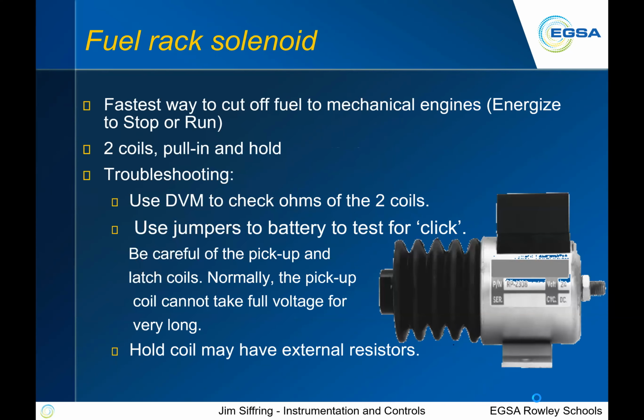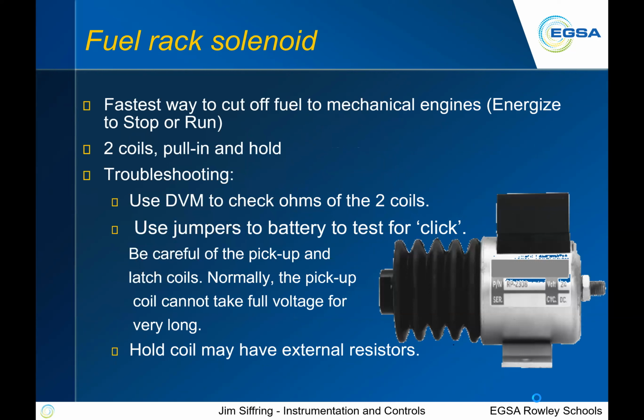Fuel rack solenoids. So, a mechanically injected engine as well. If you've got a mechanical engine, you can put this on the back of the rack and it'll either push it in and hold it, or pull it in, hold it shut. So again, troubleshooting is a lot of times just checking the coils in the thing. A lot of times these things will have two sets of coils. One is the energize and one is the maintain. And again, once in a while, they'll have an external resistor for current limiting.